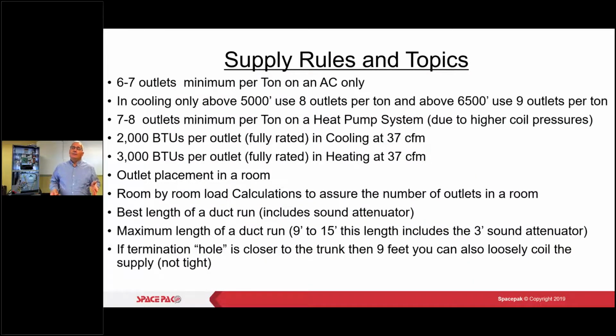So how many outlets per ton? I've been doing this for 30 years with SpacePak, and it's always a moving target. So it's 6 to 7, 7 to 8. Gentlemen, I'm picking 7 outlets per ton. That seems to always be what it averages out. So you can see 6 to 7 outlets minimum per ton on AC only. Go with 7, all right?